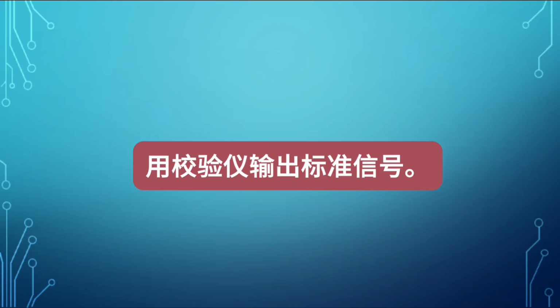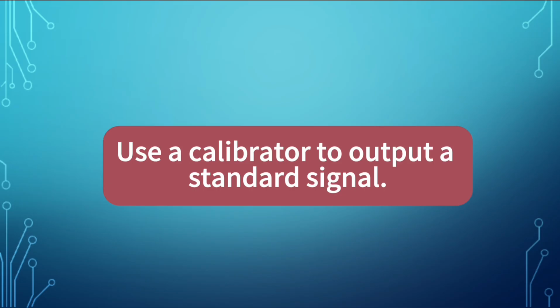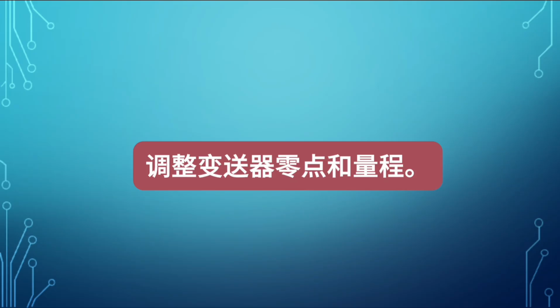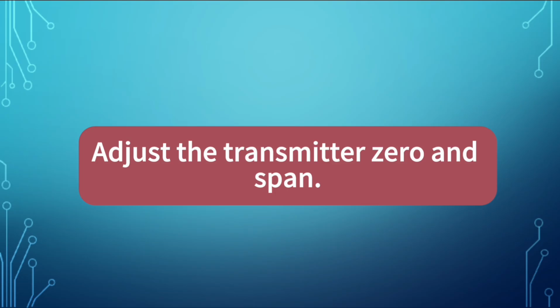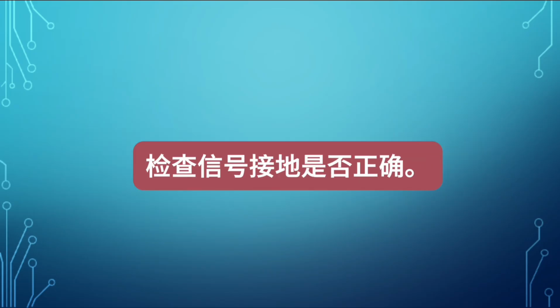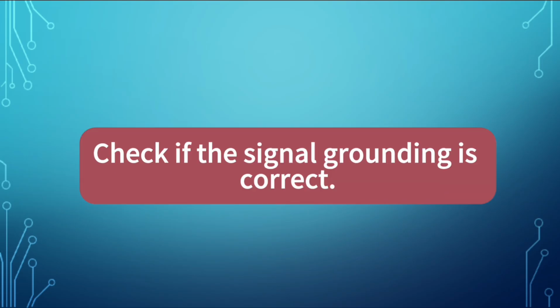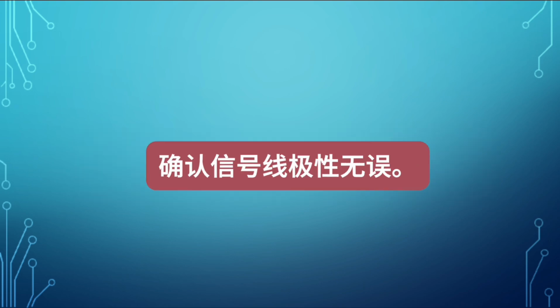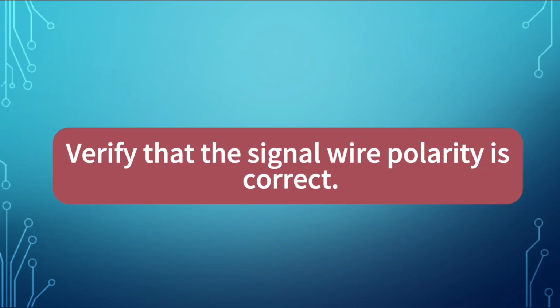Use a calibrator to output a standard signal. Adjust the transmitter zero and span. Check if the signal grounding is correct. Verify that the signal wire polarity is correct.